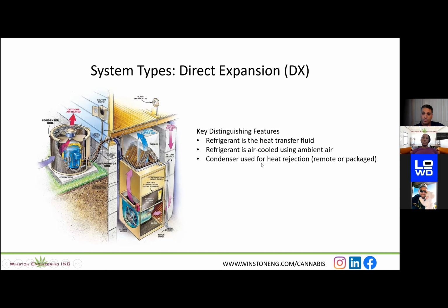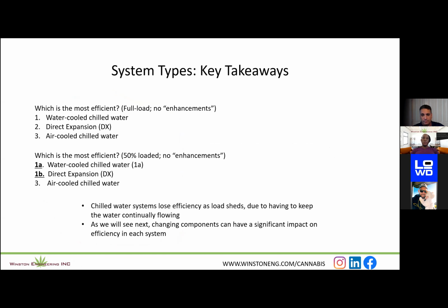Also in this case, the refrigerant is air cooled using ambient air. So the condenser is used for the heat rejection. So similar to the cooling tower in that respect. So between these three different, well, really two systems, three different variations, if you will, the key takeaways in terms of efficiency when you're looking at making selections are this. If you're looking for efficiency, generally speaking, this is high level, right? We're not digging down into the weeds because there's all different avenues we could go down with that.